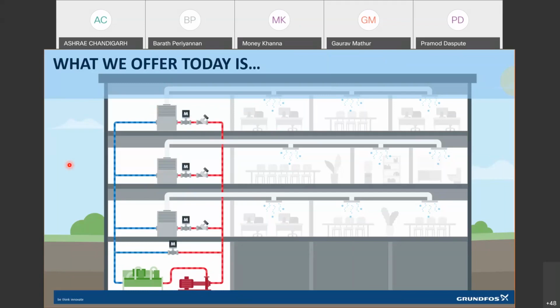But for ease of understanding, what we are essentially seeing is that there is a pump pressurizing the entire circuit. And the takeaway from this slide is only that you have a set of pumps in the plant room which are pressurizing the entire circuit. And for the flow control of individual AHUs or FCUs, what we are using is the throttling mechanism.